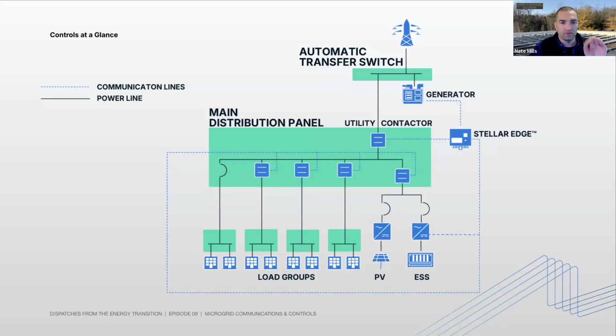As soon as the power goes out, the utility contactor will open. We have components that do that, typically not the Stellar Edge, typically something else, like an SEL 751 that the utility has experience with and believes in, and everybody is comfortable with. So the utility contactor opens automatically.